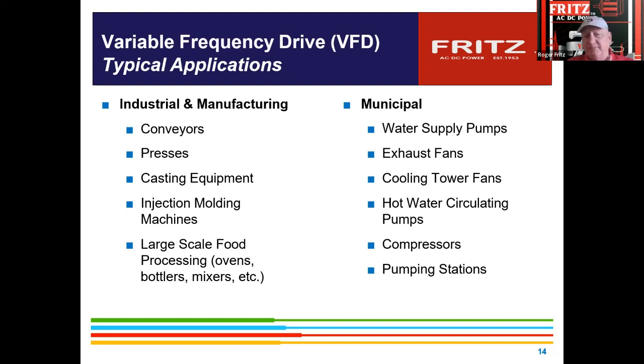Been involved in a lot of municipal business, water supply pumps. There are a lot of what they call Parco valves that are put in front of them to eliminate water hammer. When you put a drive control on, you can take that valve out and get rid of those losses across that head. Plus, you're able to stabilize the pressure and voltage, so you don't have to have pressure regulation valves on the output of the system. A lot of exhaust fans, cooling tower fans, process chilling water.